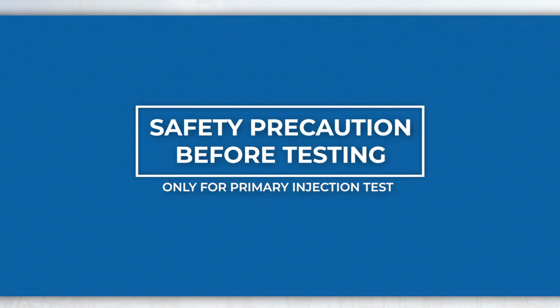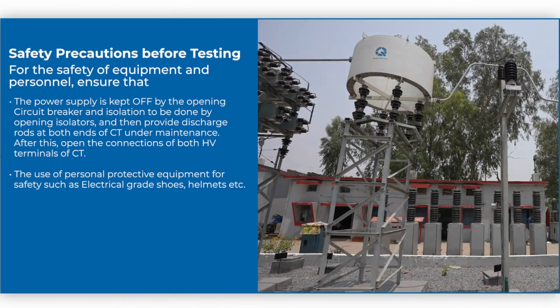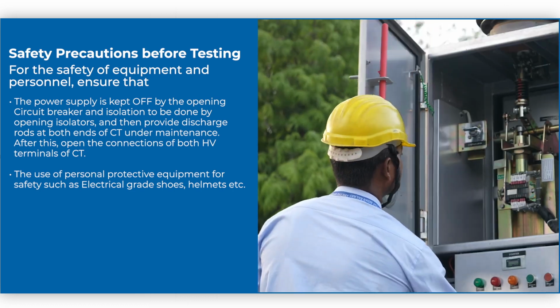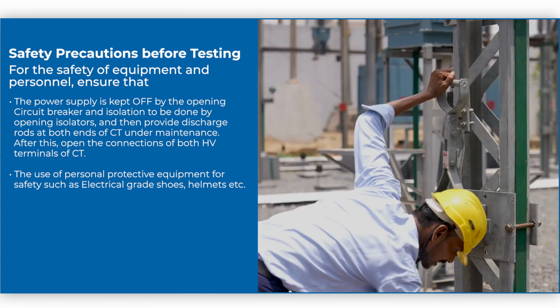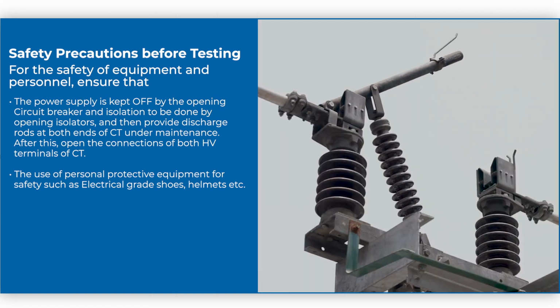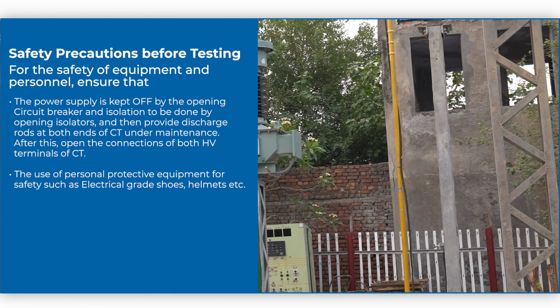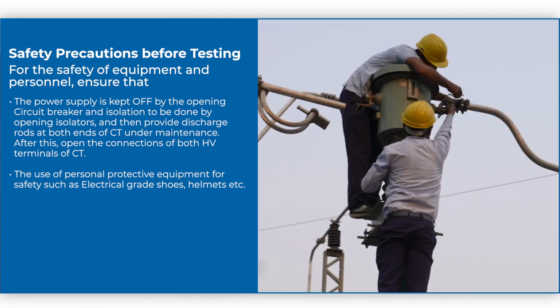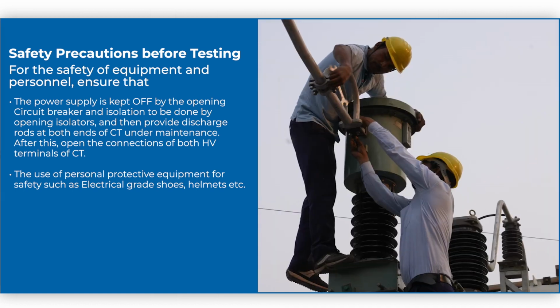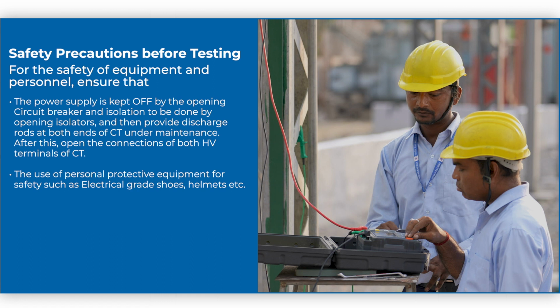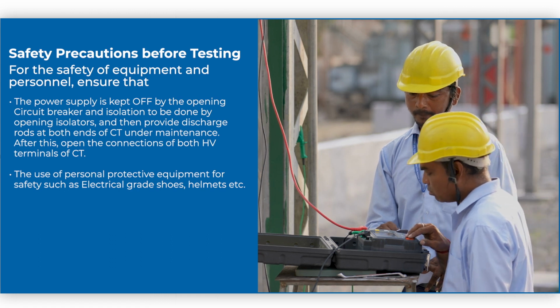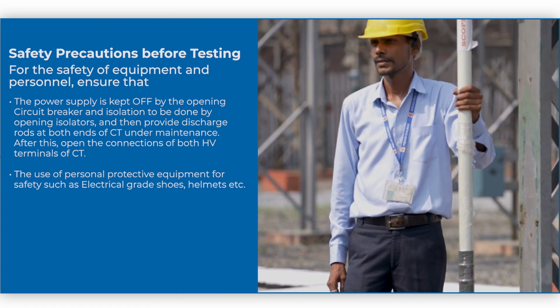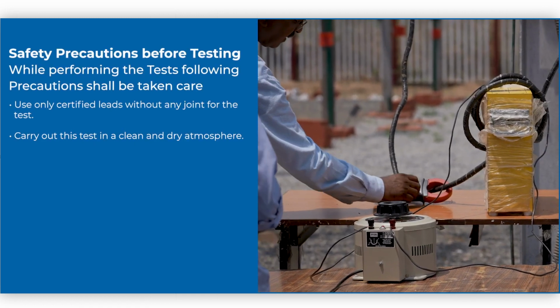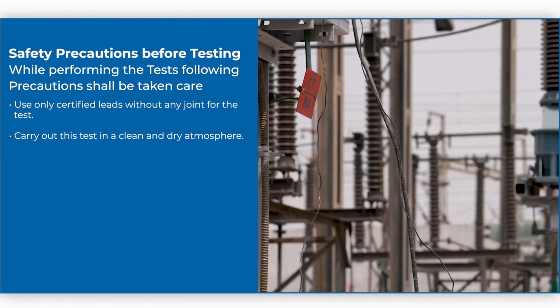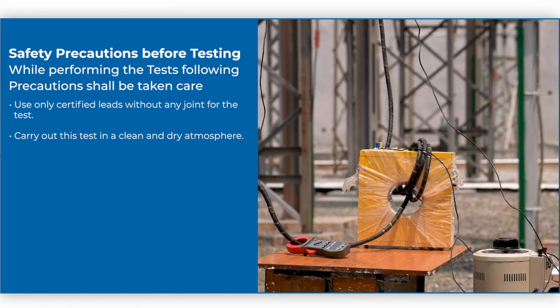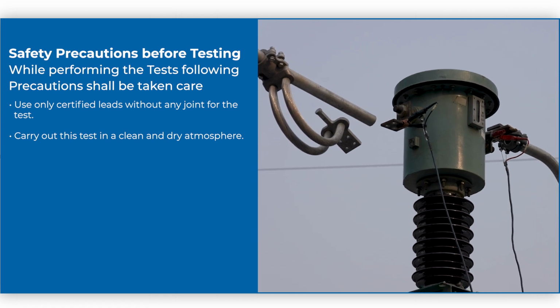Safety precautions before testing. For the safety of equipment and personnel, ensure that the power supply is kept off by opening the circuit breaker and isolation to be done by opening isolators, and then provide discharge rods at both ends of CT under testing. After this, open the connections of both HV terminals of CT. Use personal protective equipment for safety such as electrical grade shoes, helmets, etc. While performing the tests, the following precautions shall be taken care of. Use only certified leads without any joint for the test. Carry out this test in a clean and dry atmosphere.